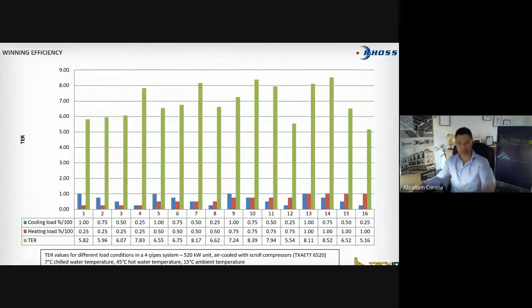What is the difference? You already have an EXP unit with all the controller, with all the advantages I told you about, the smart simultaneous independent cooling and heating, right? But it could happen that your building has unbalanced load. You may need, I don't know, 600 kilowatt of cooling, maybe 400 kilowatt of heating. When you select a heat pump, could be EXP or a standard heat pump, the cooling and the heating capacity are quite balanced. There is always more heating. Let's say you have 200 kilowatt of cooling, you may have 240 kilowatt of heating, but they're quite similar.